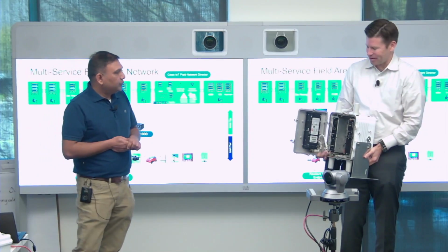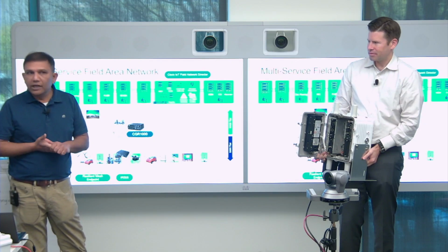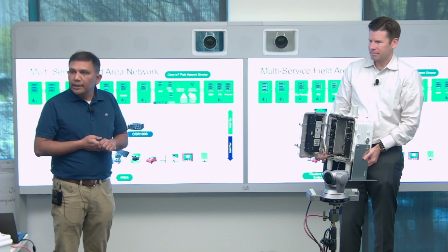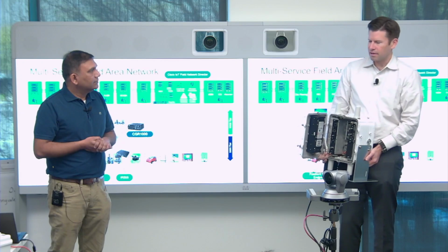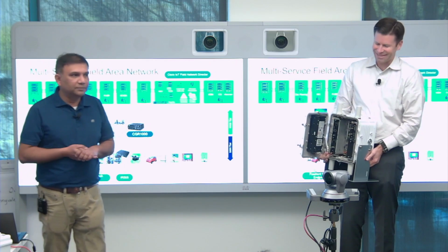Right. It's got battery backup. It can continue to operate for up to 8 hours without power. And it's an outdoor device, so it's hardened for extreme elements: negative 40 to plus 85. Yeah, so the most extreme, we've deployed this in northern Canada, British Columbia Hydro, where it has actually gotten down to negative 40. Is it Celsius or Fahrenheit? That's Celsius.